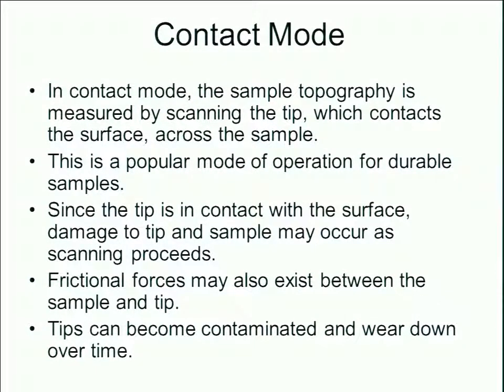In contact mode, the sample topography is measured by scanning the tip, which actually makes contact with the surface and is then scanned across the sample. This is a fairly popular mode of operation, used primarily for hard or durable samples. Since the tip is in contact with the surface, damage to the tip and the sample may occur as scanning proceeds. We can also gather information such as frictional forces, which may exist between the sample and tip, seen due to the pitching or rolling of the cantilever and laser beam deflection on the detector.